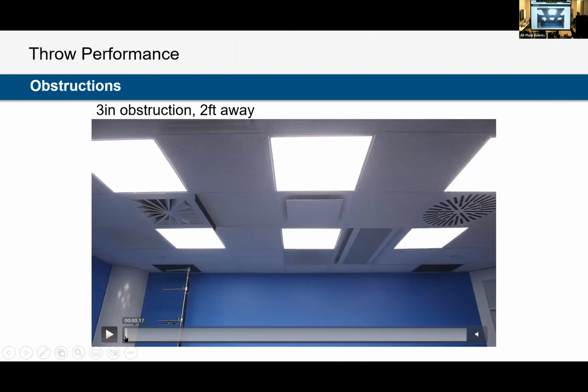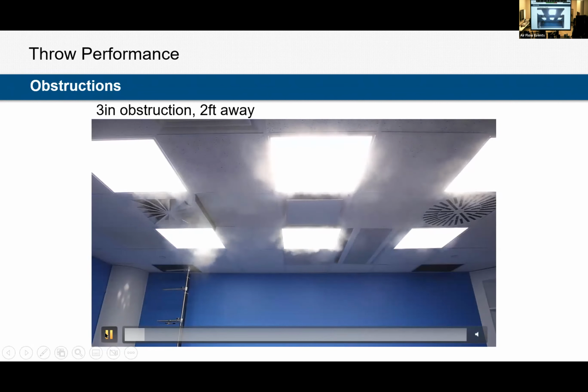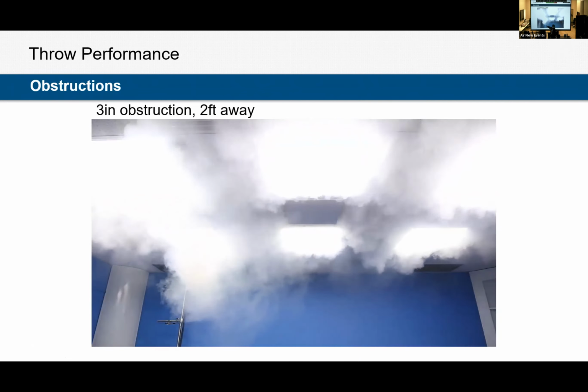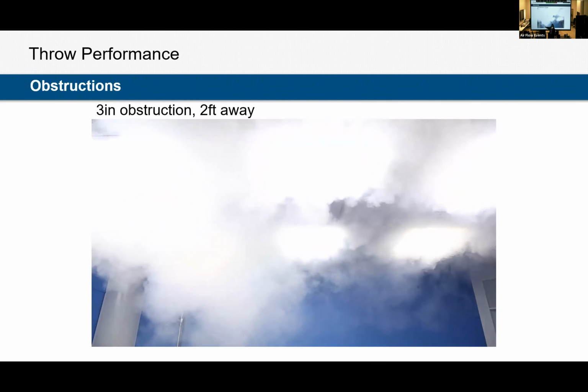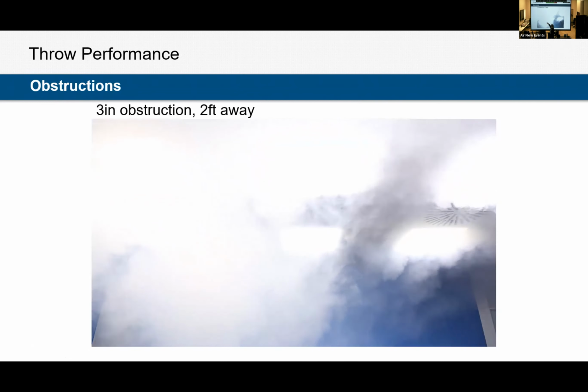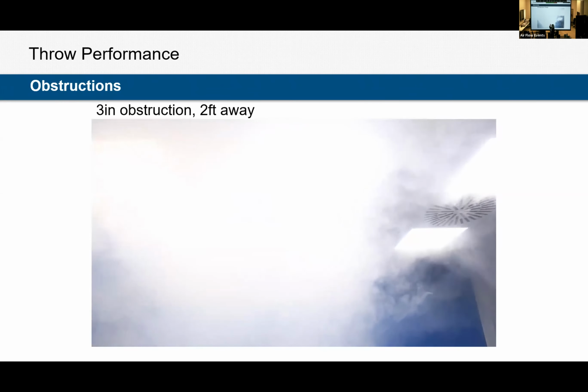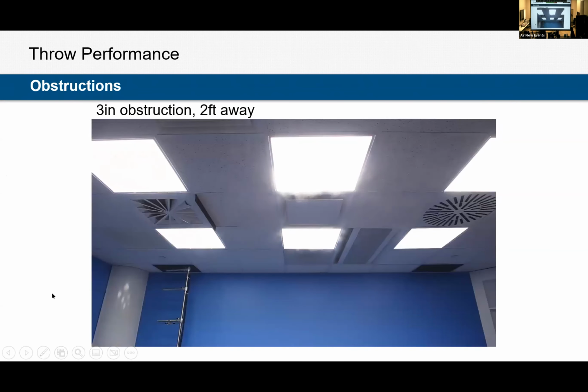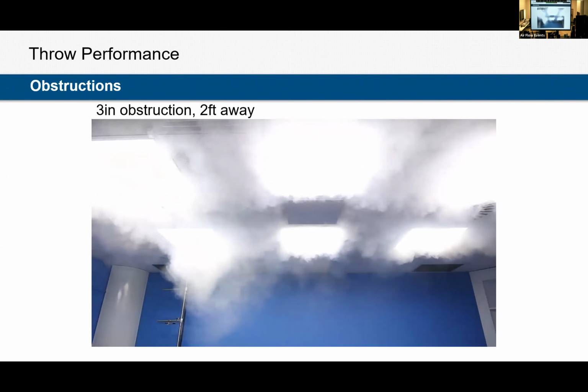Now, if that obstruction were 3 inches, a little bit longer, and that angle is greater than 10 degrees, we are actually going to see the air drop from the ceiling and shoot straight into the space. Imagine if your desk was right here. That would be awful. Just be blasted with cold air all day. So that obstruction is not allowing Coanda to happen. It's forcing the air in a different direction, which is down into the space. That room smoked up pretty quick. Play one more time. You can see that dropping.